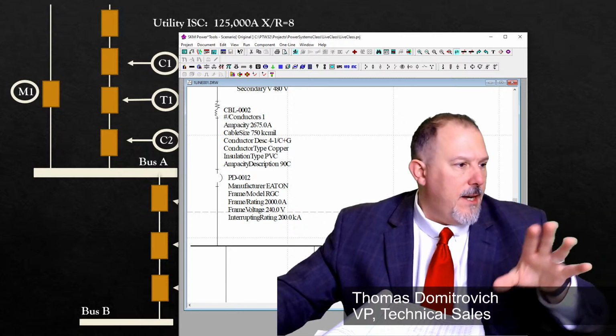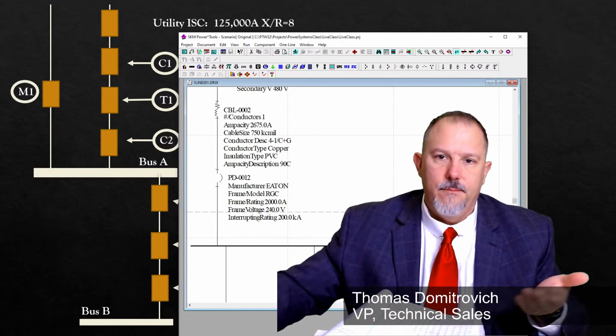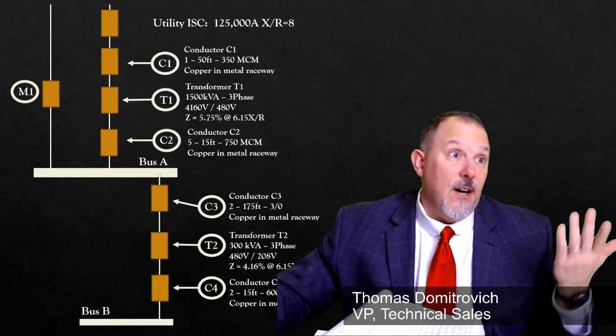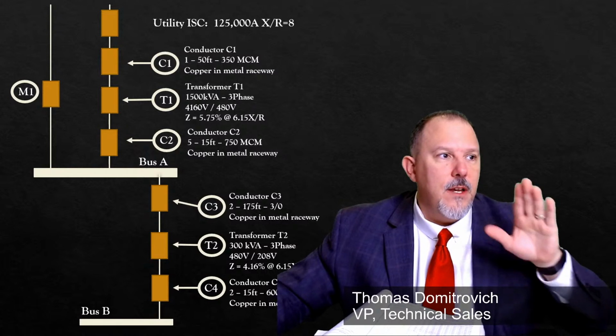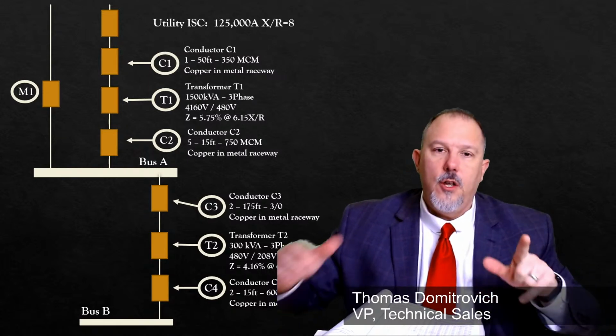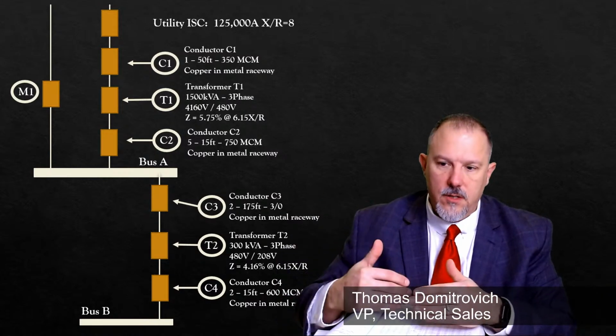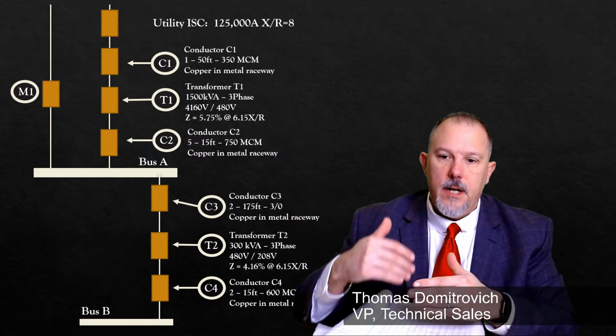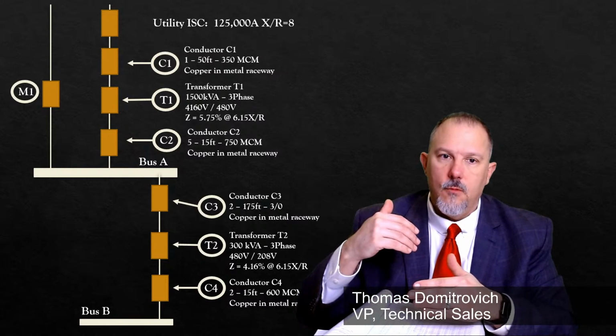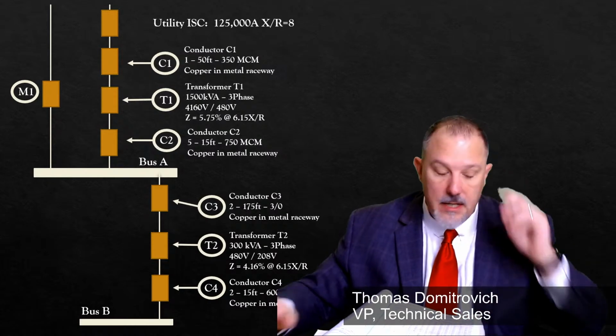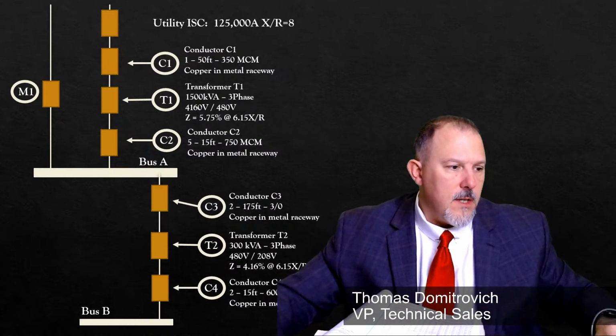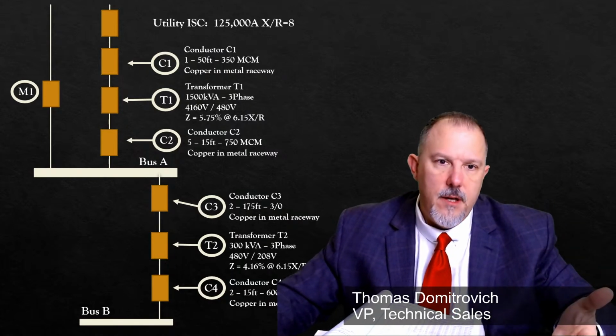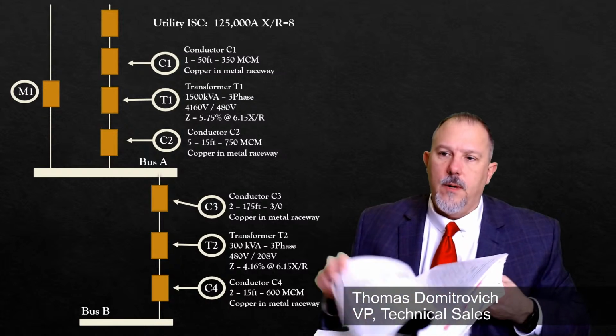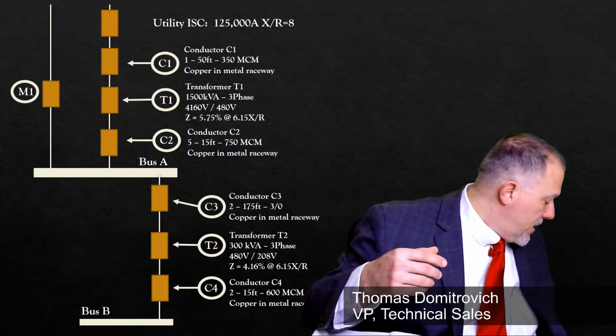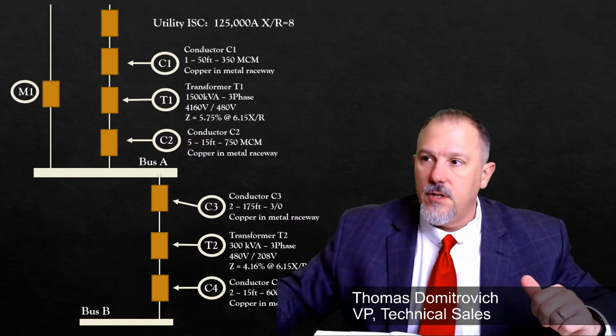So you've got two tools for you to calculate. Both of my little tools that I made for myself, basically. We calculated the ground fault currents based upon using positive, negative, and zero sequence currents, and we created the impedance diagram. The only difference that you'll have to think about is if you're going to throw the motor in. You can do the math, and if you run it and want me to run it here on SKM, I'll send you the report and run your example, and you can compare your numbers.